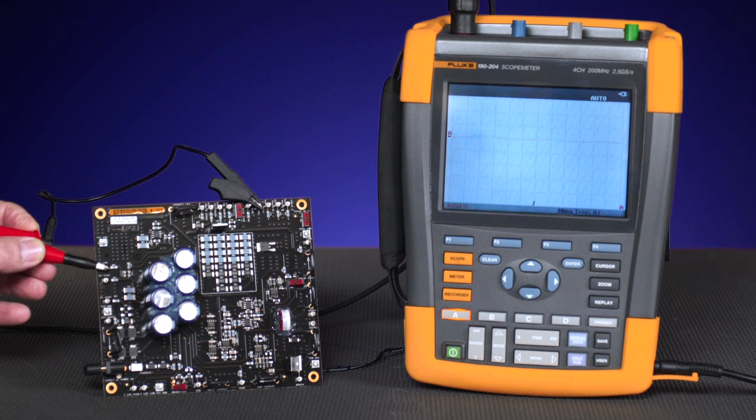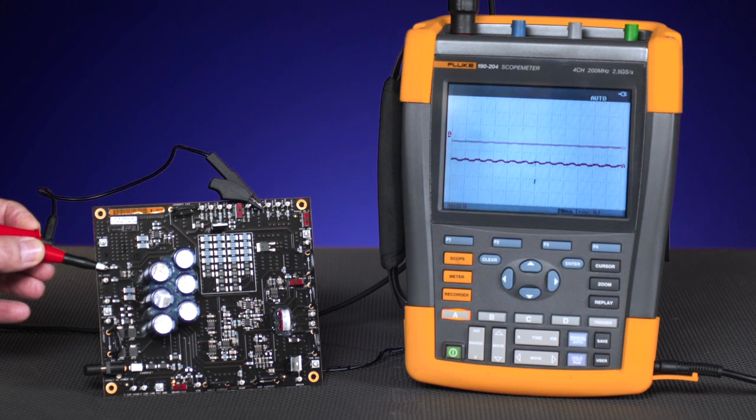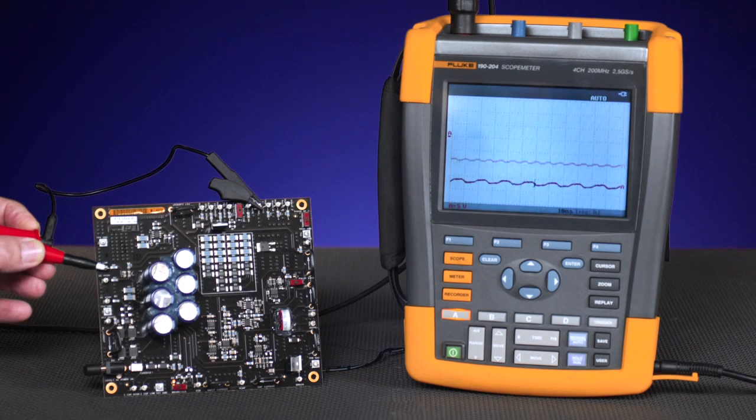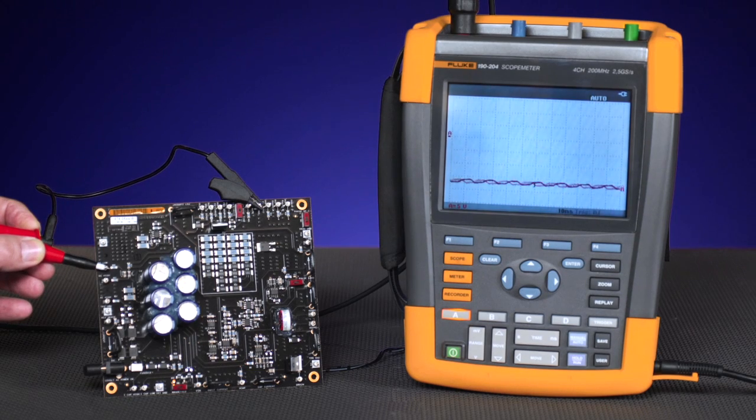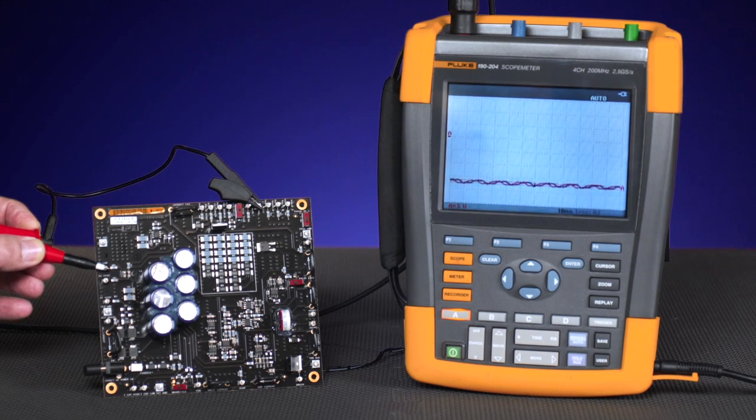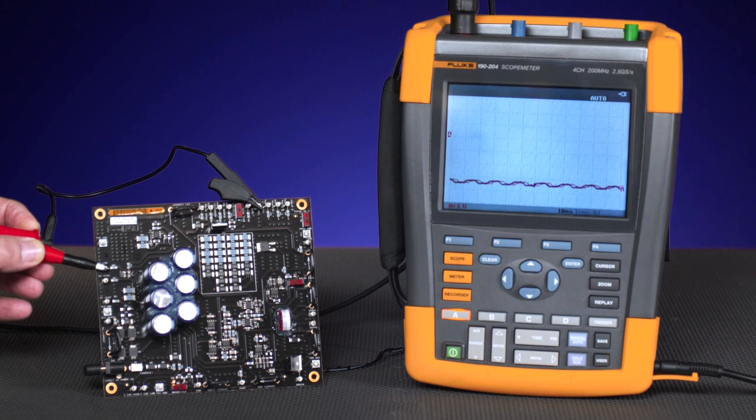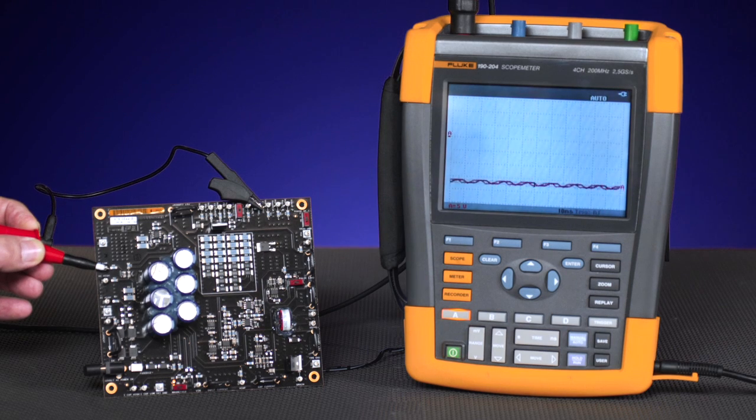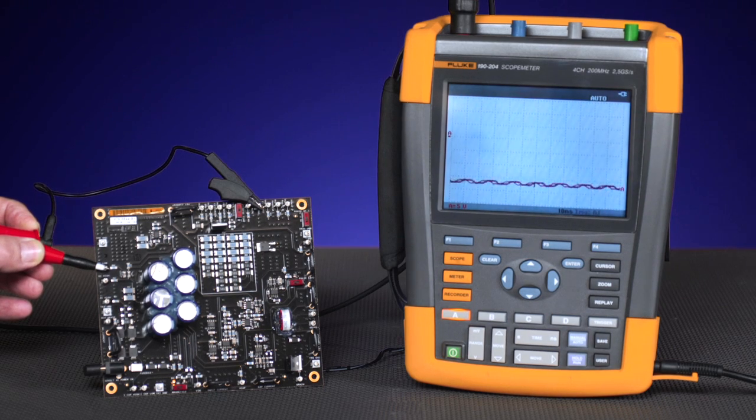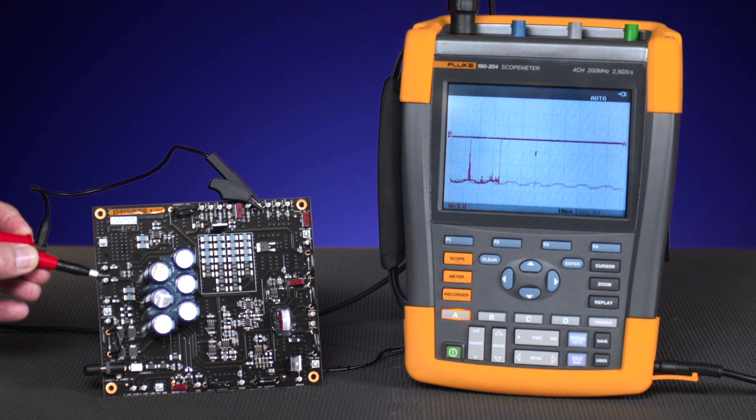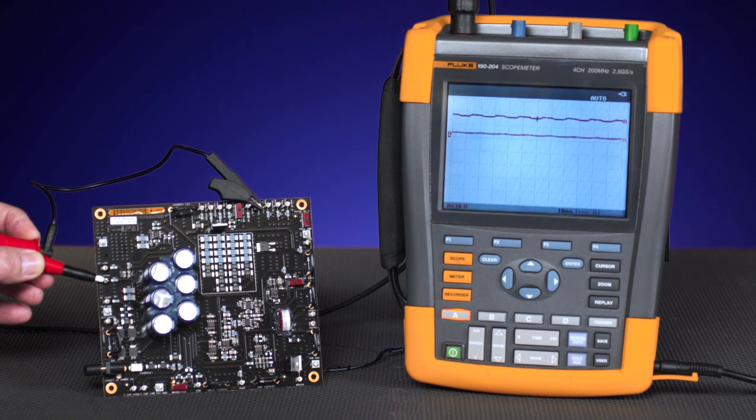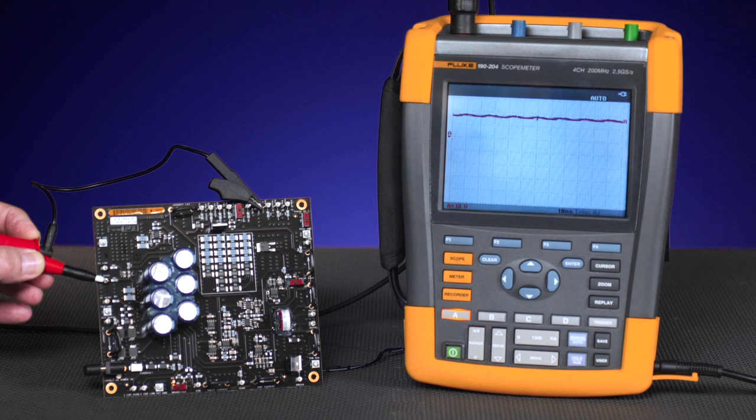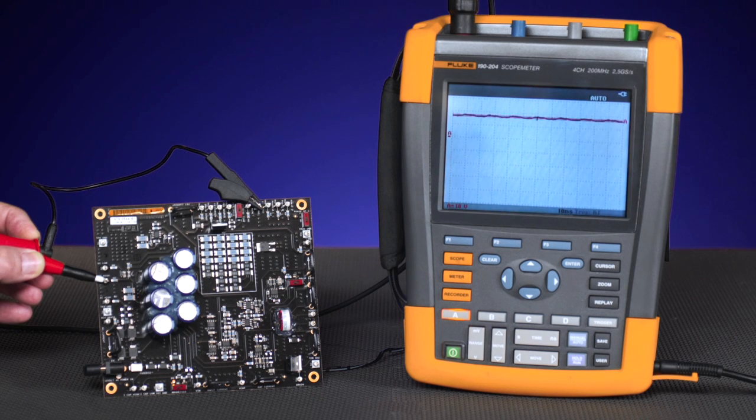Here I'm probing on the DC bus negative or low signal, looking for any signs of distortion or dropout of the signal. Moving to the DC high signal, again, inspecting for any potential problems on the DC signal.